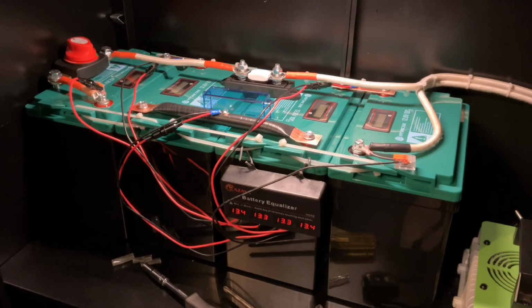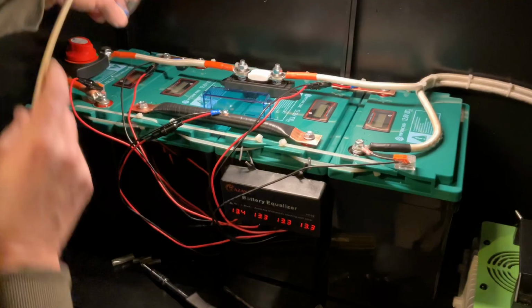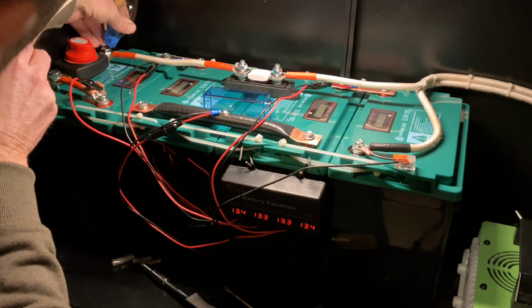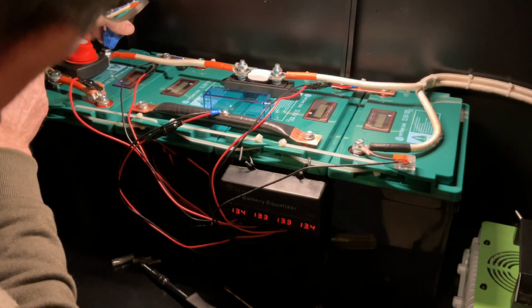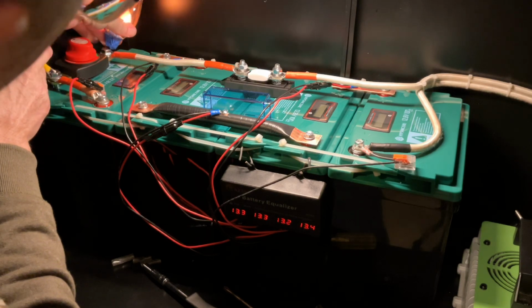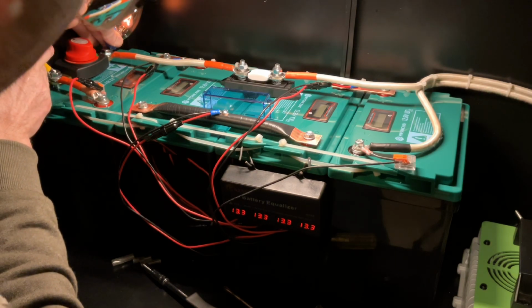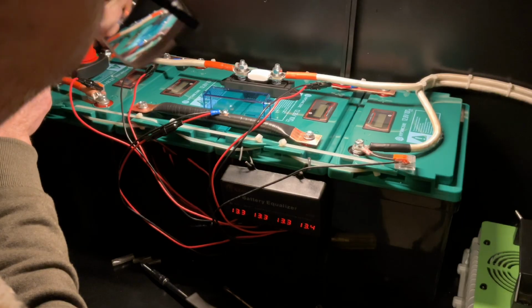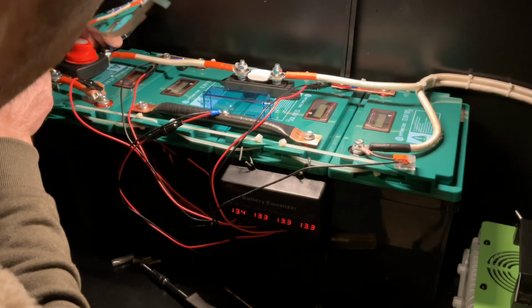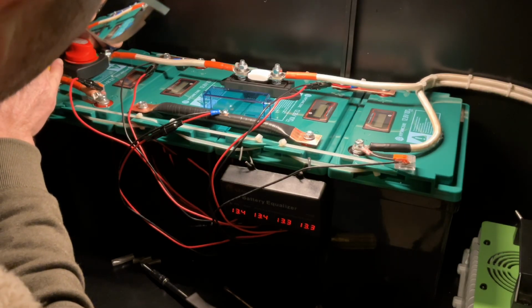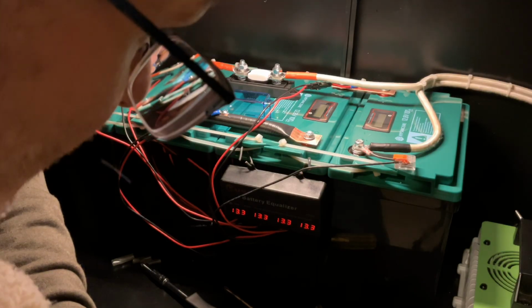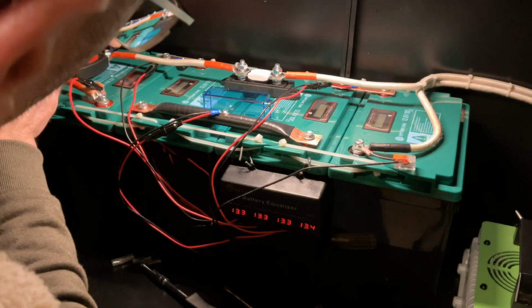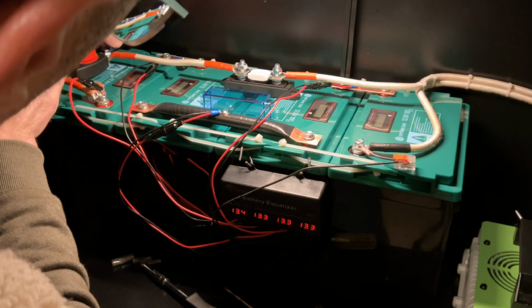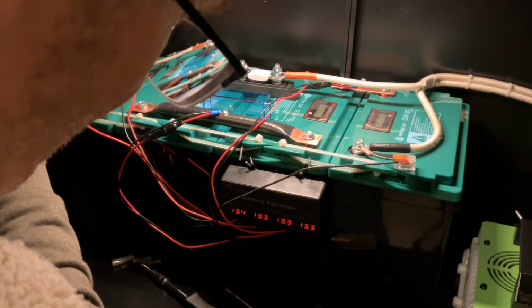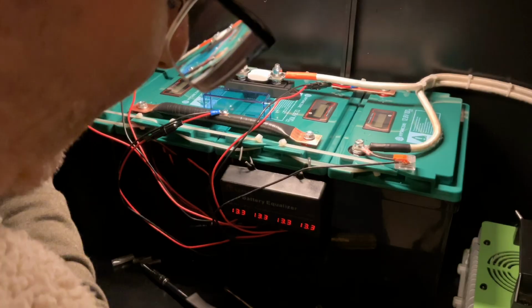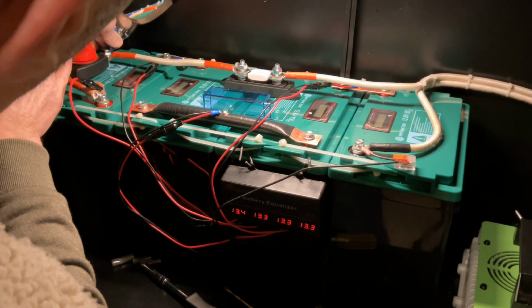All you have to do is put your light on one side of the shutoff switch and touch your wire to the other side. You'll see the light, and that's actually the current flowing through. This is a 115 volt AC light bulb, just a generic one, and it slowly charges the capacitors in the inverter prior to turning on that switch, so you don't get that huge surge current. It's not great on electrolytic capacitors to get that big inrush surge like that.